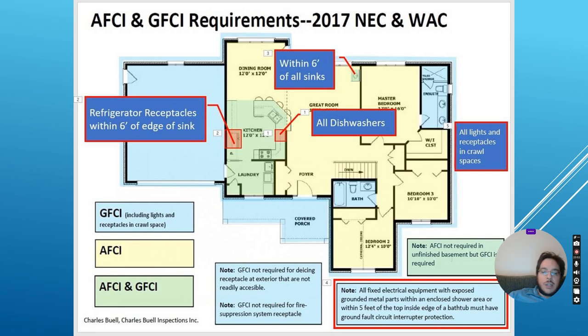So now check it out. If we look at a typical house, pretty much everywhere in the United States now requires an AFCI breaker. Any circuit that feeds receptacles or lighting in any living area, so dining room, master bedroom, kitchen, laundry, requires it. The only places that don't need it are the outdoors, the bathrooms, and the garage. Those just need GFCI breakers, and everybody else needs AFCI breakers. And remember, the kitchen and the laundry room need AFCI and GFCI breakers.